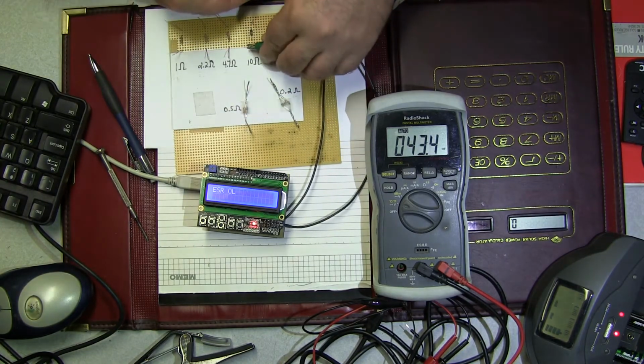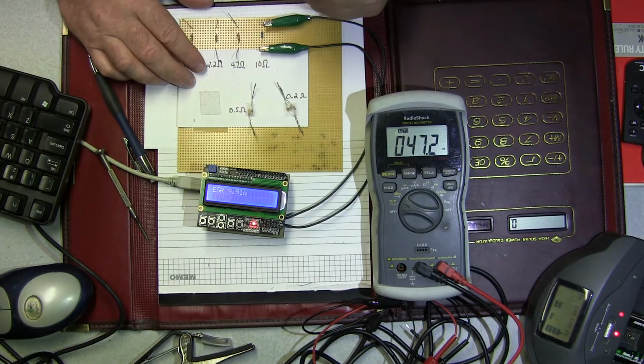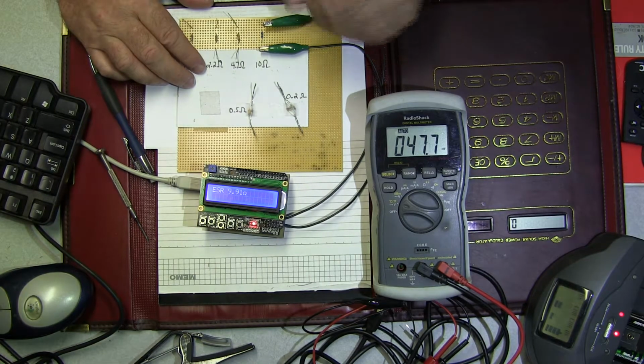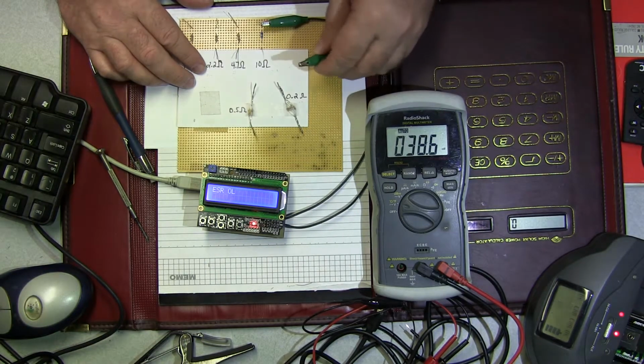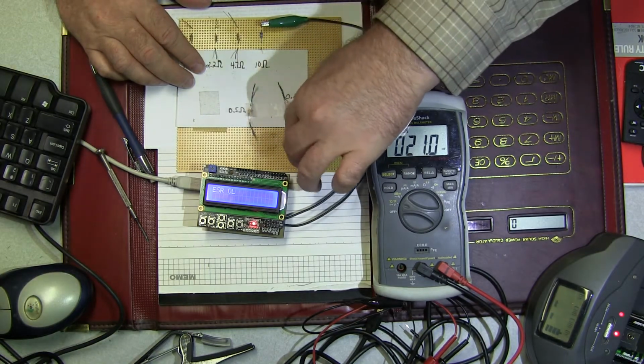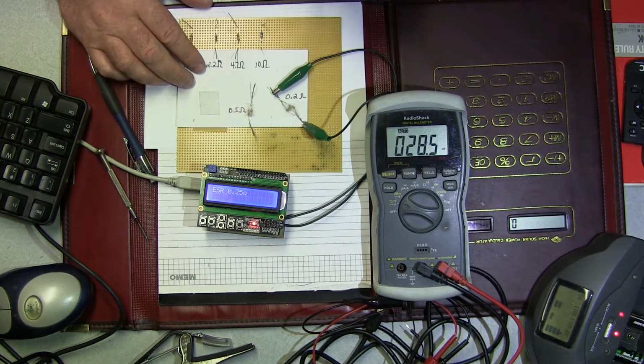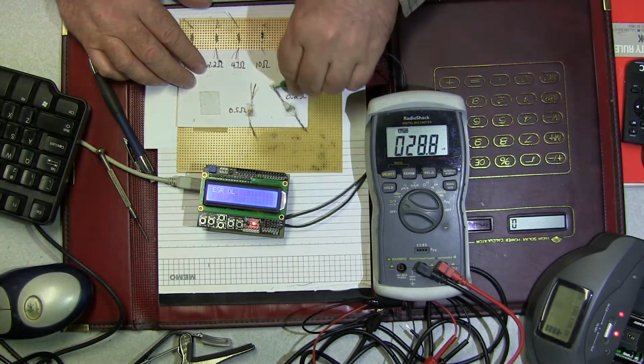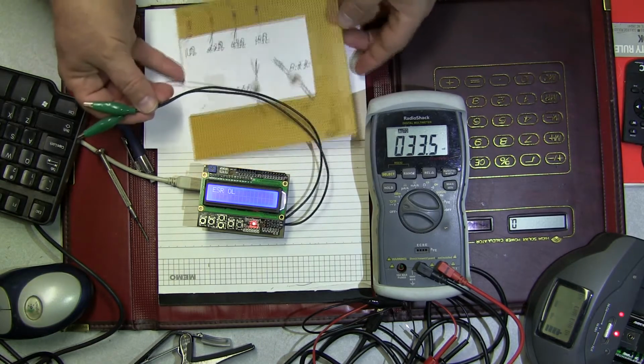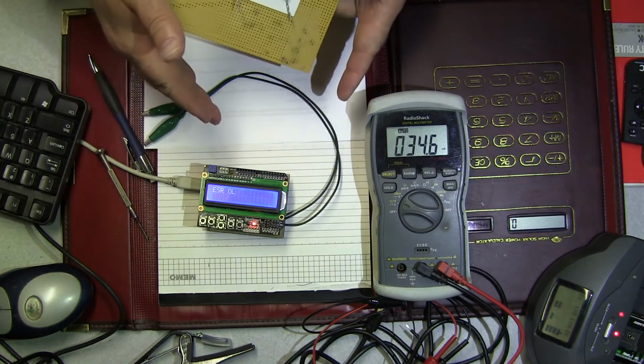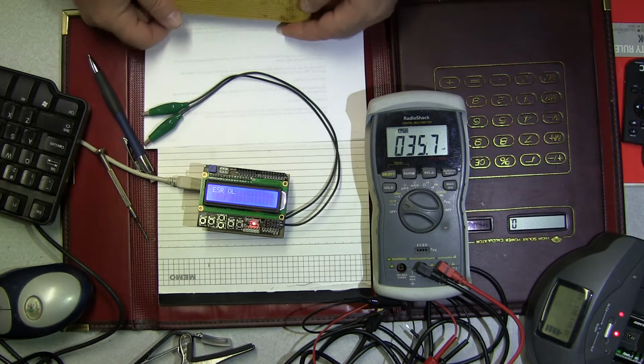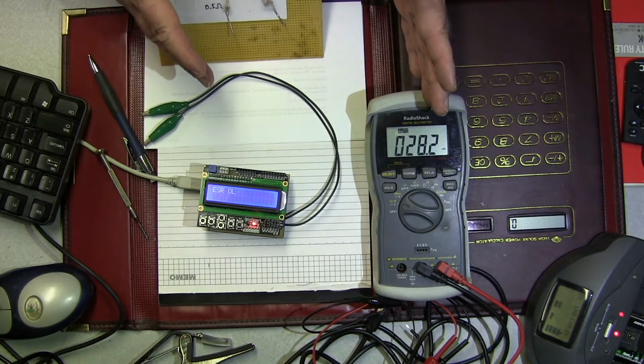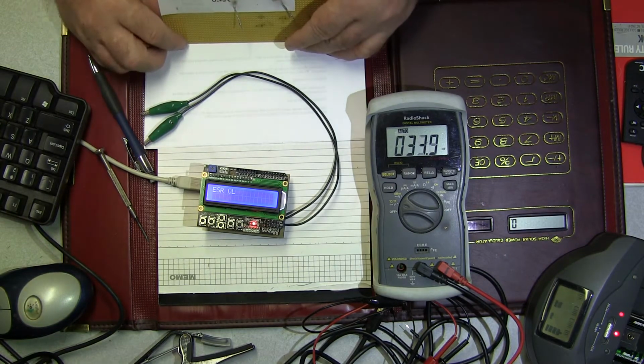Now if I connect it back to my 10 ohm resistor, it's going to read 9.91, 9.95 flashing, which is close enough. If I get down here on my 0.2 resistor, it's bouncing 0.22, 0.20. So even though my initial setup values have drifted, the calibration function in the code will keep it calibrated. You don't need to go back and reset these values every time, and I really don't know how far the values have to shift before it throws it out of calibration. I haven't ran into that yet, and I've had this up and running for several months now.